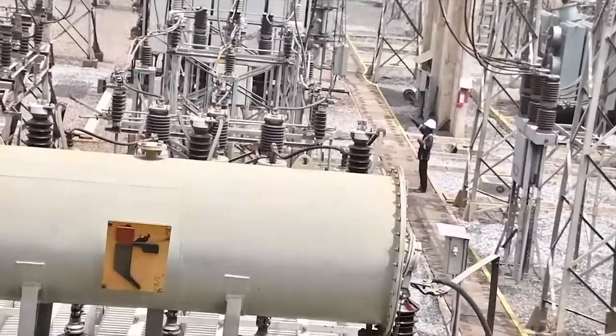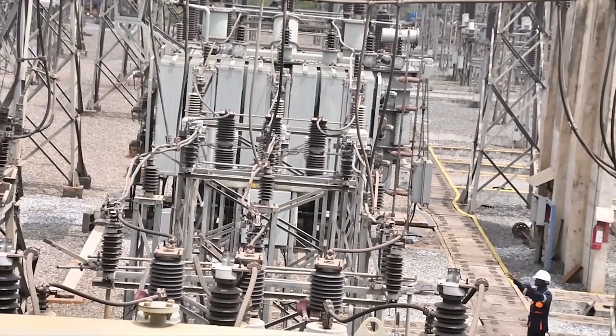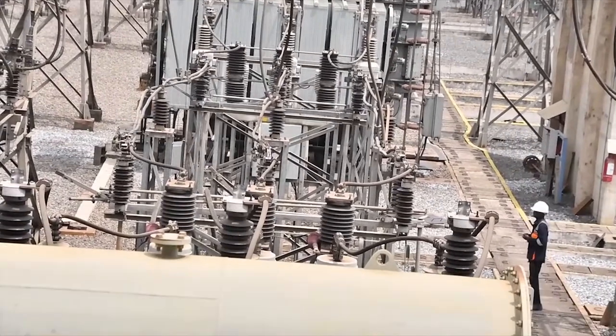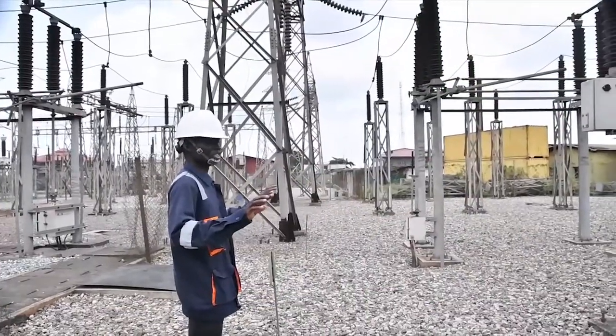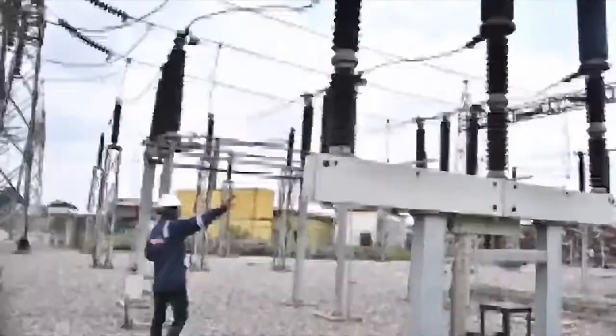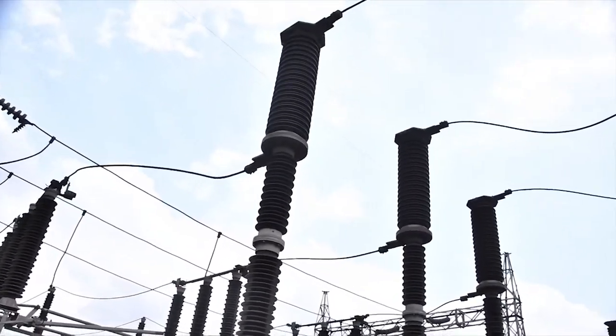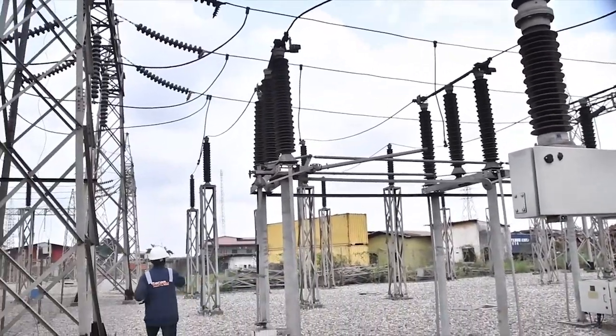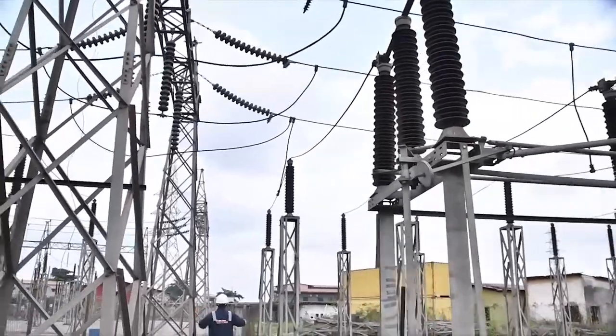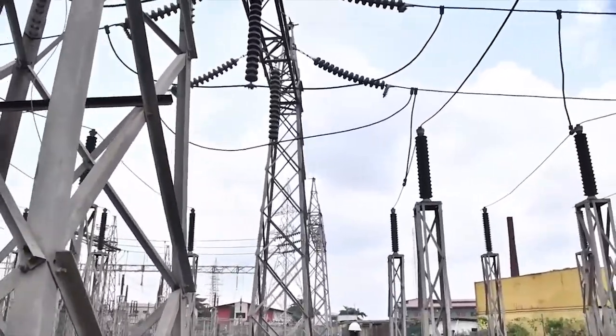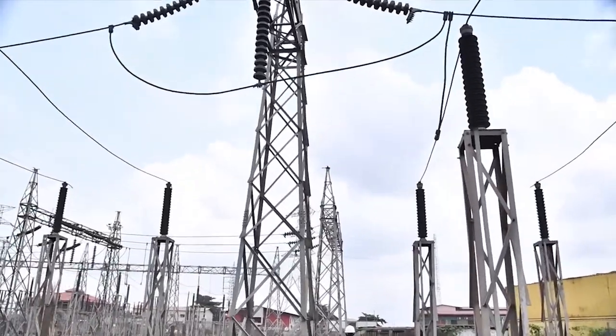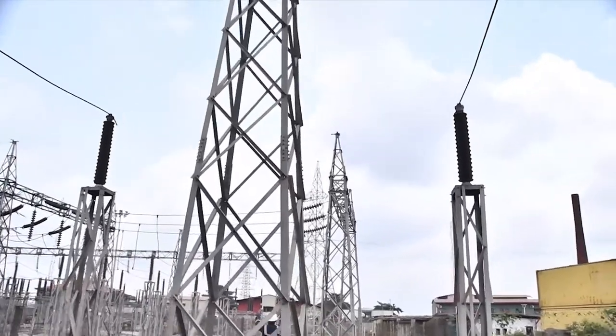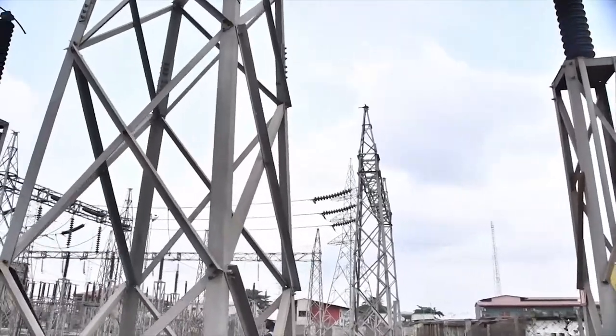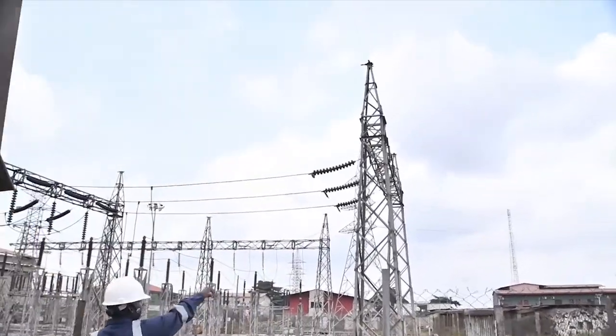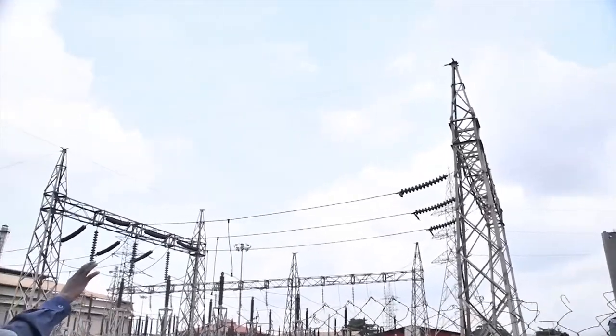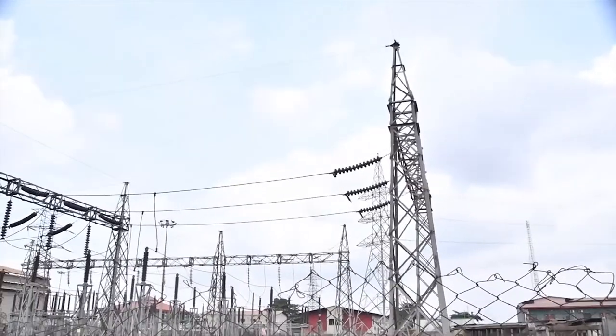We used our own hands to install all this equipment, and I'm happy to say that all this equipment is in good condition. This is the 132 kV section. You can see our SF6 circuit breaker, our isolators, and our insulators. This is where we connected to the national grid — you can see the marks here. This is the point where we connected to the 132 kV national grid line.